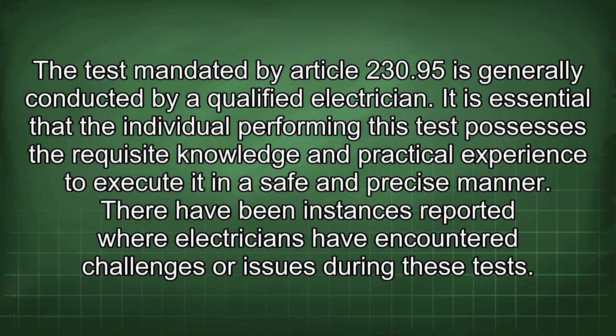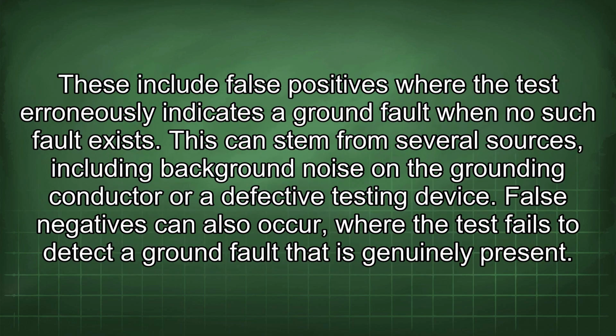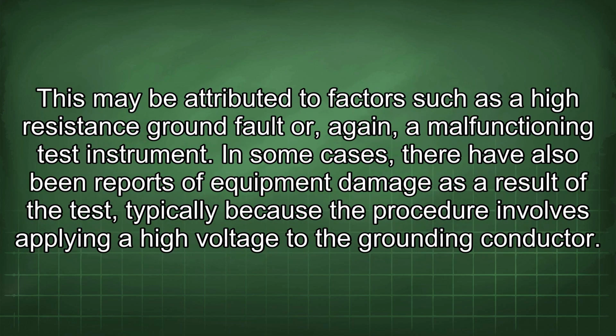There have been instances reported where electricians have encountered challenges or issues during these tests. These include false positives where the test erroneously indicates a ground fault when no such fault exists. This can stem from several sources, including background noise on the grounding conductor or a defective testing device. False negatives can also occur where the test fails to detect a ground fault that is genuinely present. This may be attributed to factors such as a high-resistance ground fault or, again, a malfunctioning test instrument. In some cases, there have also been reports of equipment damage as a result of the test, typically because the procedure involves applying a high voltage to the grounding conductor.